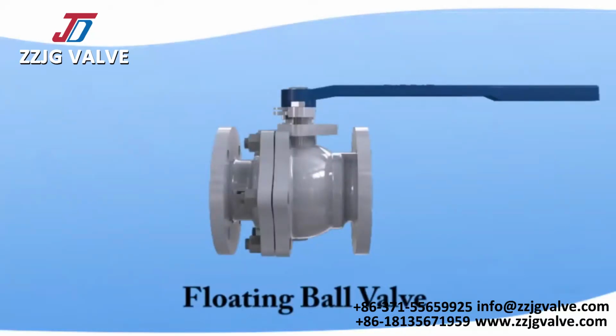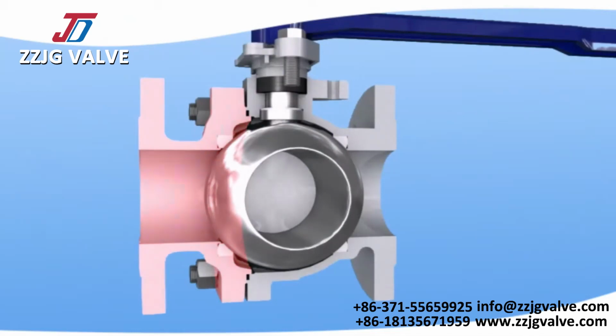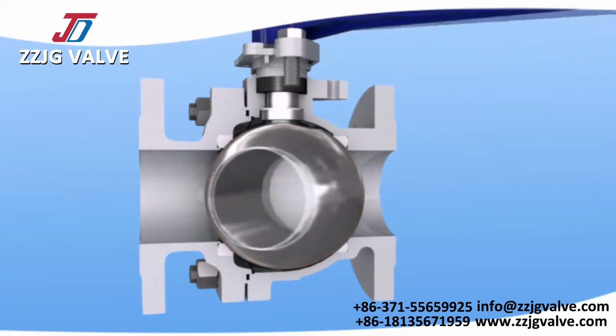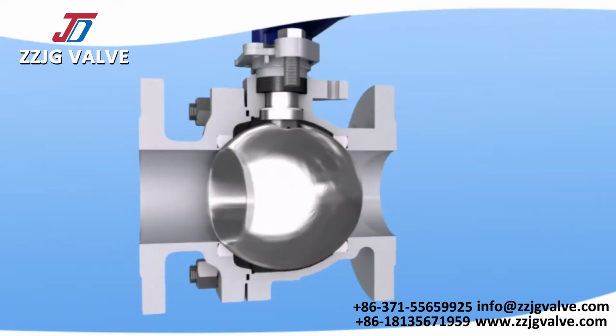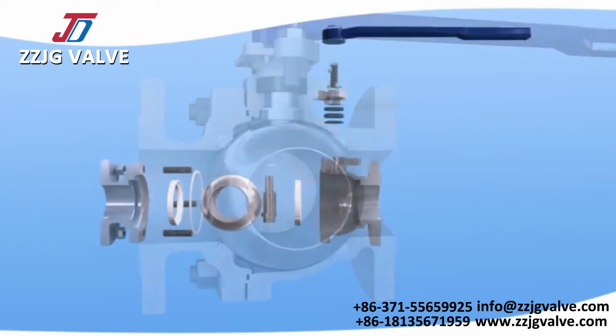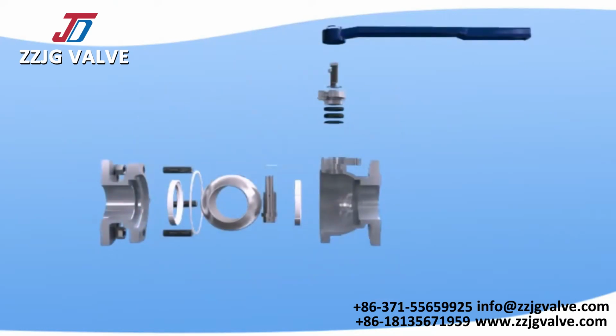Floating ball valve. A floating ball valve has two sealing seats. There is a ball between the seats. The ball can rotate inside the seat ring by the stem.